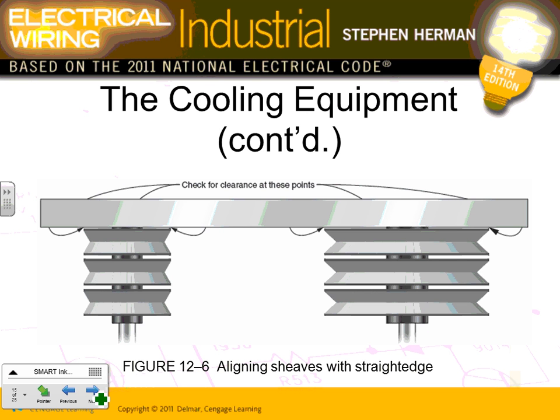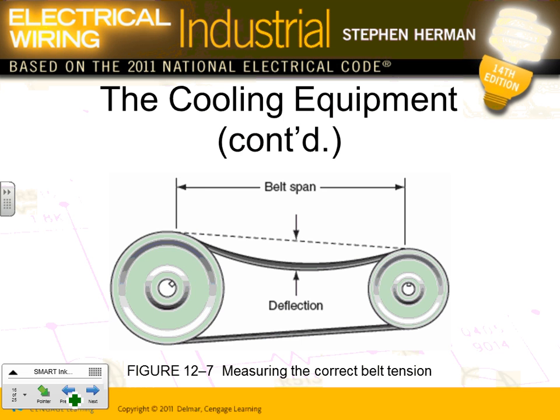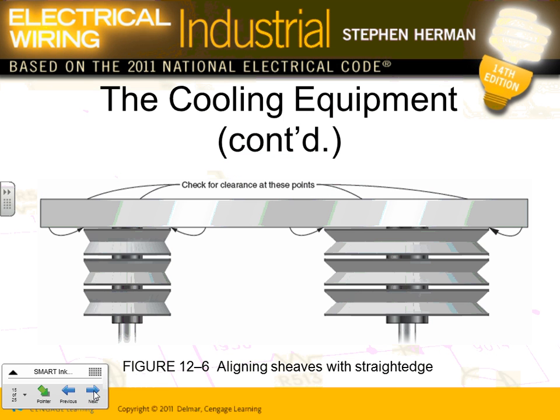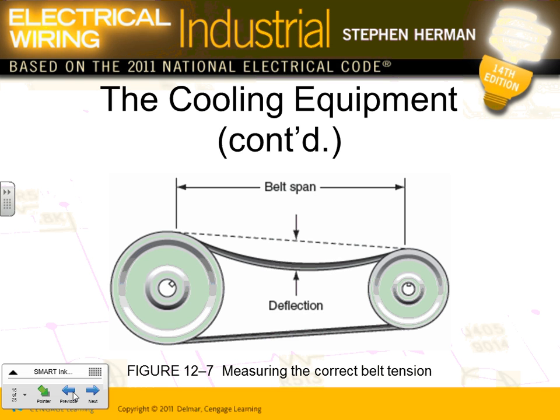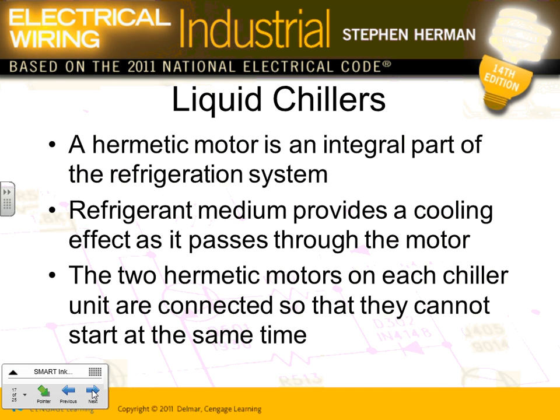And then aligning sheaves with the straightedge, we'll skip that one. Typically not. If they need power factor correction, the manufacturer will add it as part of the package. Cooling equipment, guys, I'm not going to go through that. This is the mechanical stuff. You have the pulleys and the belt and deflection. If you open these, there's a belt that drives the fan. The motor is mechanically interfaced with the fan, either by direct connection or through a belt. If it's through a belt, you have to make sure the deflection is within acceptable range.